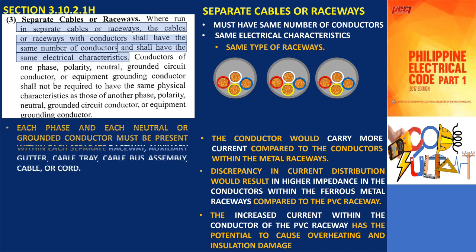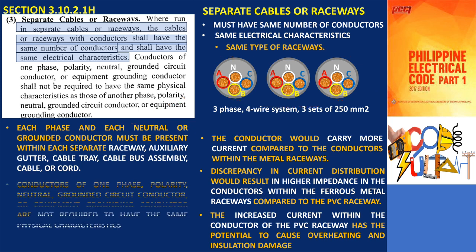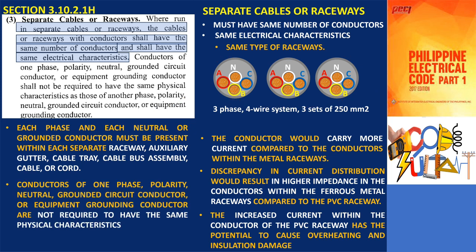Additionally, each phase and each neutral or grounded conductor must be present within each separate raceway, auxiliary gutter, cable tray, cable bus assembly, cable, or cord. In the illustration shown, a three-phase, four-wire system where three sets of 250 mm² conductors are paralleled for each phase and the neutral. There should be one 250 mm² conductor for phase A, one for phase B, one for phase C, and one for the neutral within each of the three raceways. This ensures proper distribution and balance of electrical current.